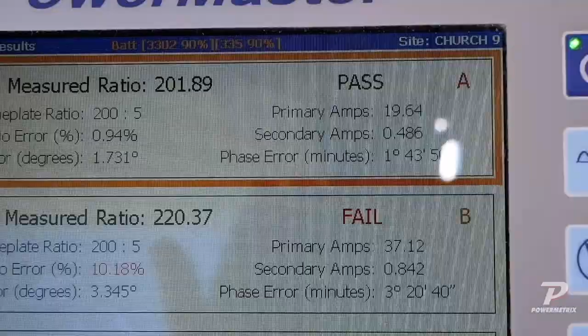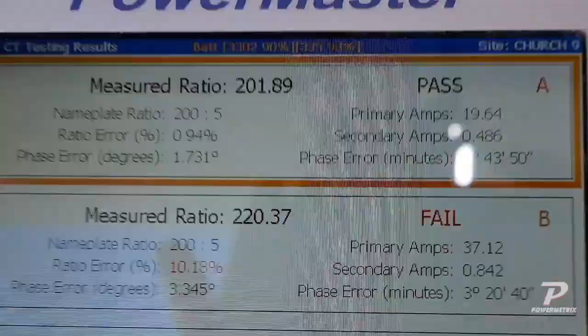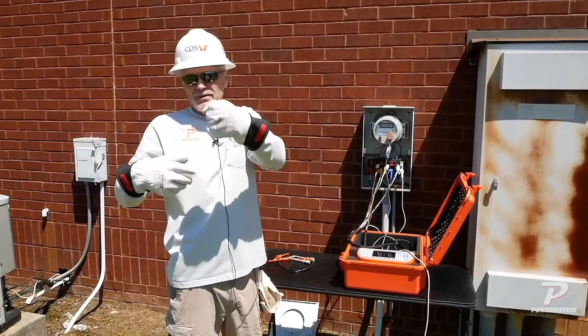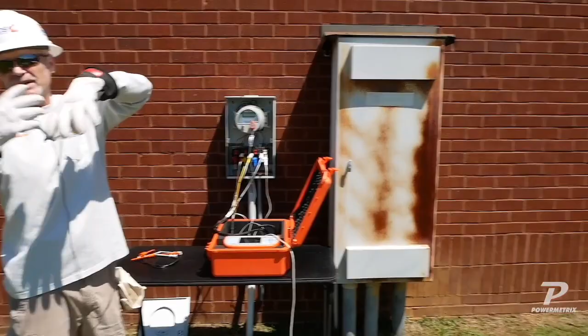The other thing to consider here is, remember, we've got two services, so we've got two sets of conductors right there beside one another. And it's not like there's total insulation all the way around those cables, because they have to peel them back to get them in those spade lugs. So you've got other magnetic fields from a different service over here, a different set of conductors going on. So sometimes you have to get good separation and try to center those flexible CTs as much as possible.